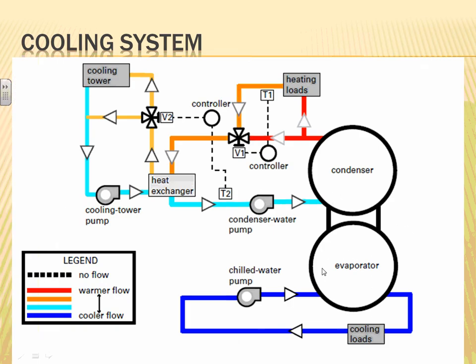So what they do, and please jump in here, help me too. Inside the evaporator, the chiller, they circulate chilled water instead of chilled refrigerant. They chill the water and circulate it to the air handling unit or units in different locations. So now we're chilling water and circulating that water to multiple locations inside the building. When it reaches the air handling unit coils, the cold coils or the cooling coils, a big fan throws air right through it in the air handling unit, and that's how you get the so-called cooling loads. So you have chilled water pumps that circulate. Now you need a huge pump to circulate that chilled water that has been chilled inside the chiller.